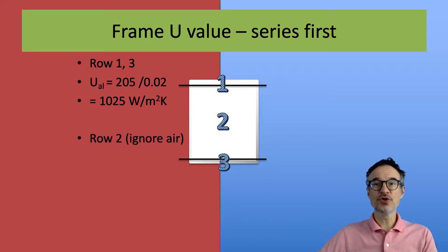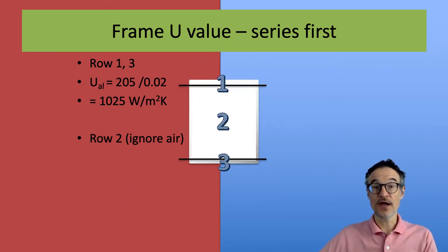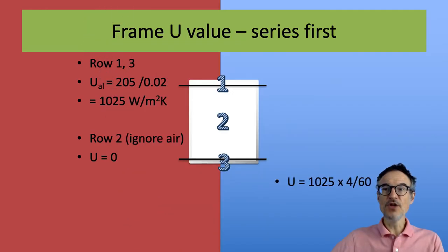And row two, we're basically saying that air is a much better insulator than aluminum. So let's just say there's no heat going through there, all the heat's going through the aluminum. So the U value is zero. Of course, it's not really zero. So we look at the ratio of the area and we get something like 68.